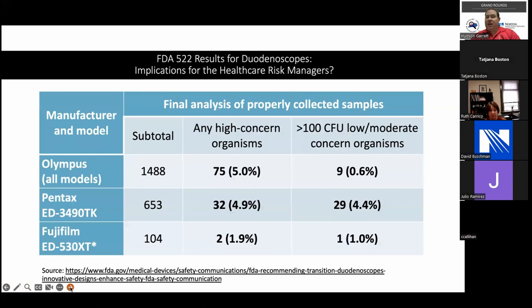But if you look at the high concern organisms, remember FDA's expectation was zero, and yet we saw as high as 5% of properly reprocessed endoscopes, all following the validated instructions for use, still had high concern pathogens. This was representative of less than 3,000 endoscopes, but it tells you there was a massive issue with device design, the training, the validation, and the actual reprocessing. FDA said, oh my gosh, what are we going to do now, because now we have data that says these devices are harming people.